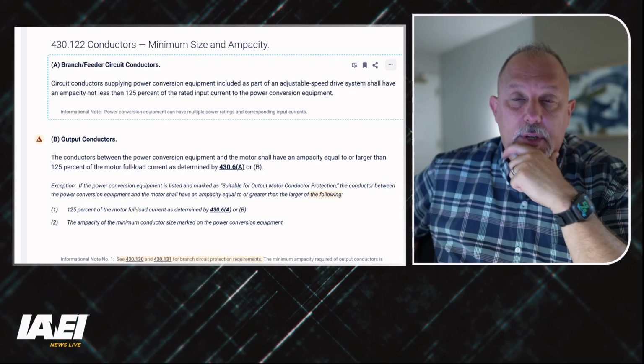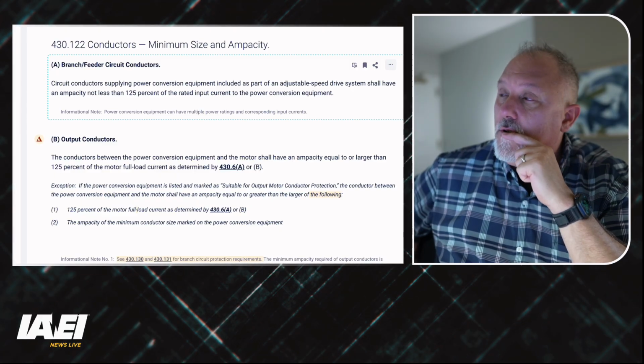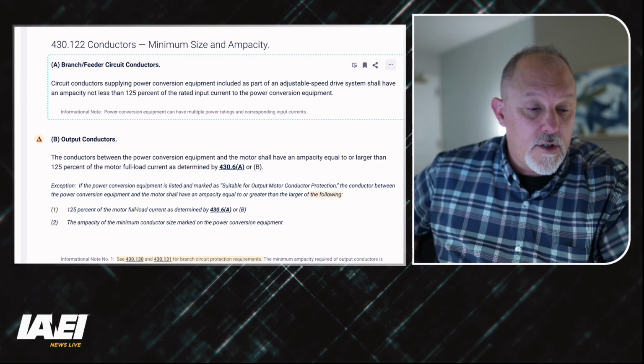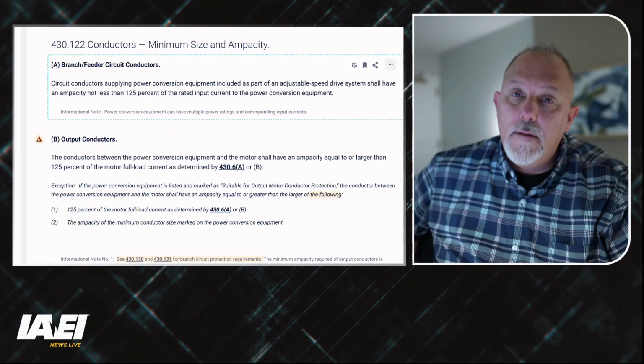I know a motor can't be a continuous load. And the reason, so let's talk about this. The reason a motor can't be a continuous load is because motors have inrush currents. And an inrush current is not going to last for 3 hours. So when you read the definition of what a continuous load is, it's the maximum current operating for 3 hours. And the maximum current for a motor is inrush.